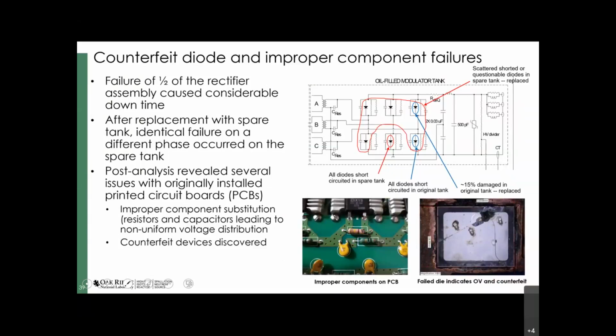Of course, when you've got a large array of up to 180 series connected diodes, once one device fails, then it just redistributes the voltage and just puts a little bit more voltage across all the remaining active devices. But if enough of them fail over time, you actually reach a point where you can no longer hold the reverse voltage rating of the diode, and then they all go, they avalanche.